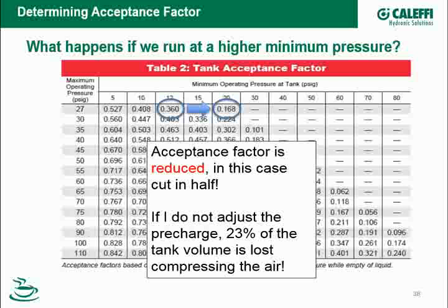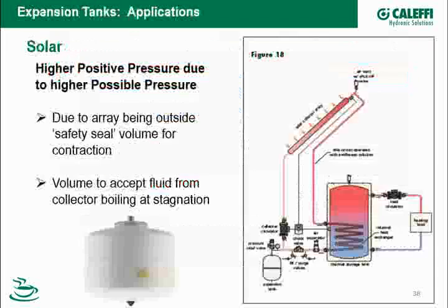Okay, solar. A closed-loop pressurized solar system will require an expansion tank. A couple of things are different in the setup and the sizing of the tank. First off, with solar, as I said earlier, we're going to run at a much higher positive pressure to suppress boiling in the collector itself. Some solar panels have stagnation temperatures of 325, 375, 425. I'm going to run at a higher positive pressure to take care of that.